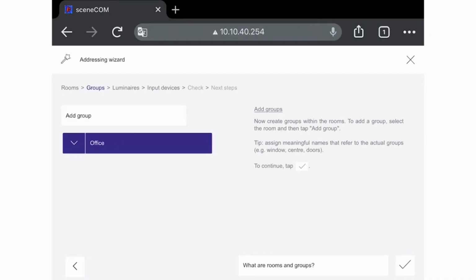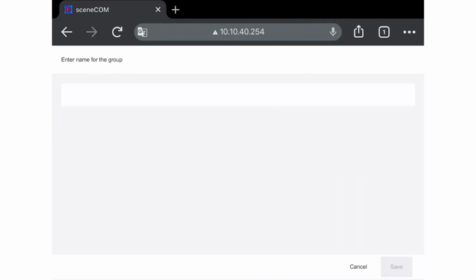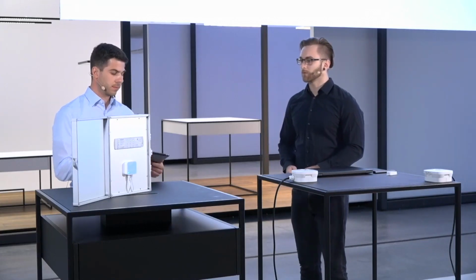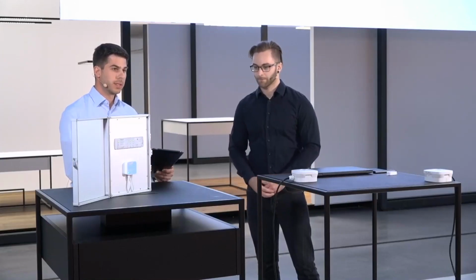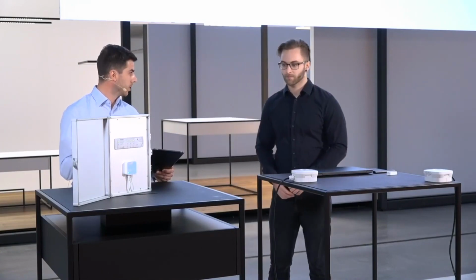And what I'm going to use is the addressing wizard. It's a simplified way to make sure to address all of the luminaires which are connected to the DALI line. So if we now go through the addressing wizard, what exactly do I need to do here? We have the wireless now. How do I set up the controller with the luminaires? As you can see in the addressing wizard, it really tells you what you have to do.